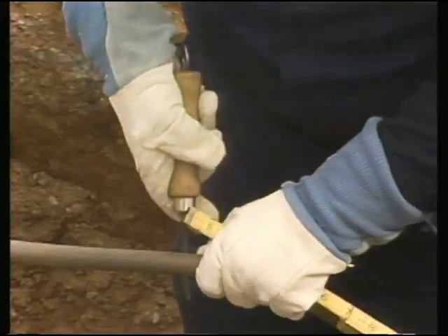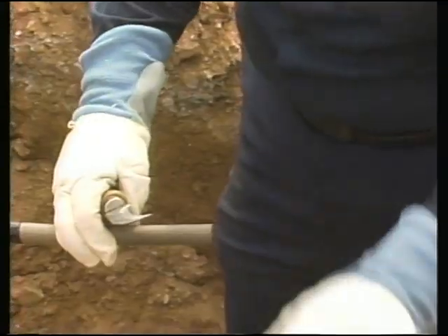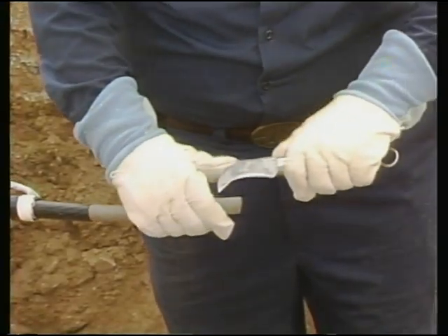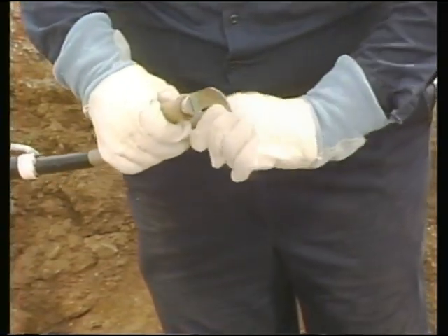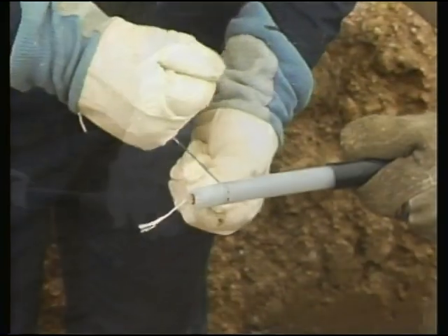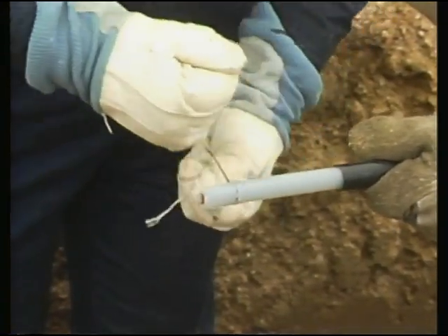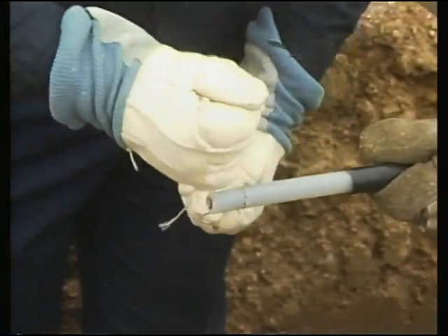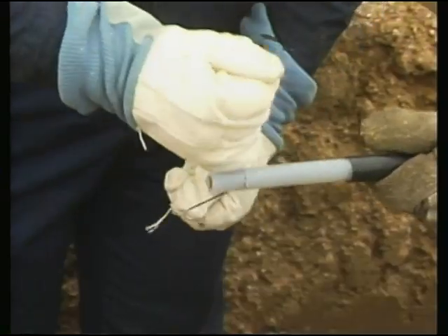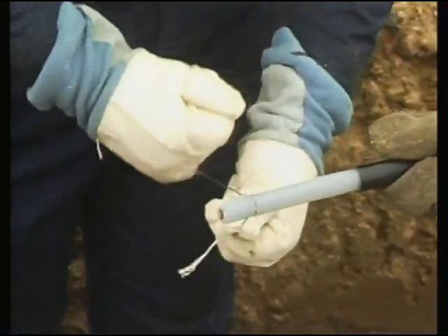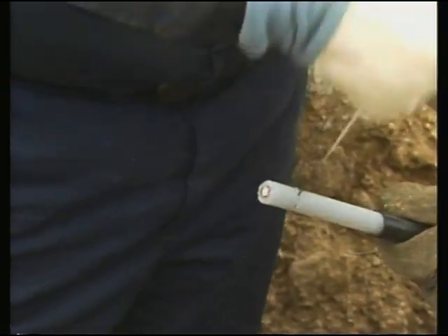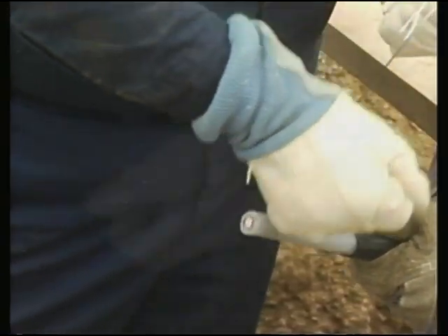First, a knife can be used to cut halfway through the insulation and then down to the end, making a weak point in the insulation that can then be pulled apart and removed. Another method, used with XLP and EPR cables, is to use a nylon string. The string makes a circular cut through both the insulation and the conductor shield layers, without damaging the conductor.